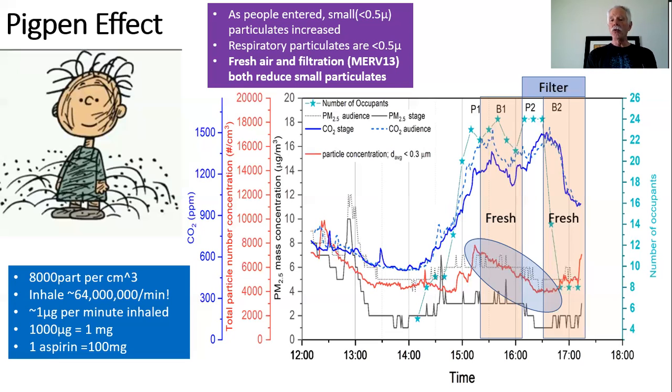Now, these are two tools that we have to reduce the concentration of contagion in a restaurant, in a classroom, in an office, and other spaces. But this is more directly in a restaurant. And I just wanted to demonstrate that in reality, we have these very important tools to get the concentration of contagion reduced. And then when we turned on both the fresh air fan and kept the filter running, we dropped the particulates down to a base level.